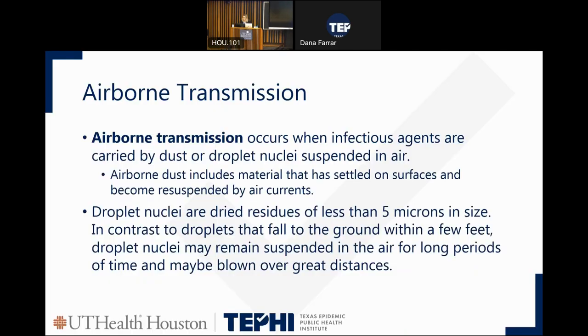Next, we're going to talk about airborne transmission. Airborne transmission occurs when infectious agents are carried by dust or droplet nuclei suspended in the air. Airborne dust includes materials that have settled on surfaces and become resuspended in air currents. Droplet nuclei are dried residuals of fewer than 5 microns in size. In contrast to droplets falling to the ground within a few feet, droplet nuclei remain suspended in the air for long periods of time and are blown over great distances, thus requiring engineering controls of negative pressure to be implemented in healthcare settings to reduce the likelihood of transmission.